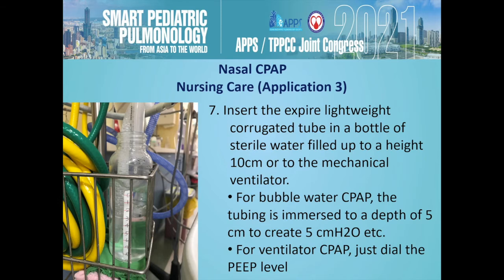Insert the expiratory lightweight corrugated tubing in a bottle filled with sterile water at 10 cm height, or just connect to the mechanical ventilator if you want to ventilate with CPAP. For bubble water CPAP, the tubing is immersed to a depth of 5 cm. It will create a 5 cm water pressure PEEP. If you immerse 6 cm depth, then it will generate a 6 cm water PEEP. For ventilator CPAP, you just dial the PEEP to the level you want.